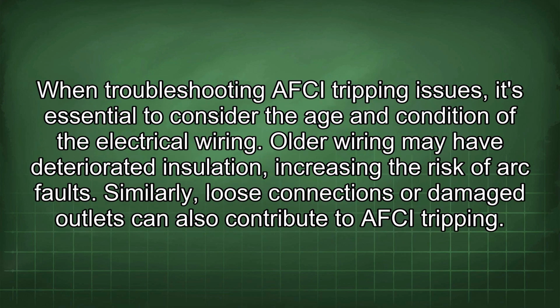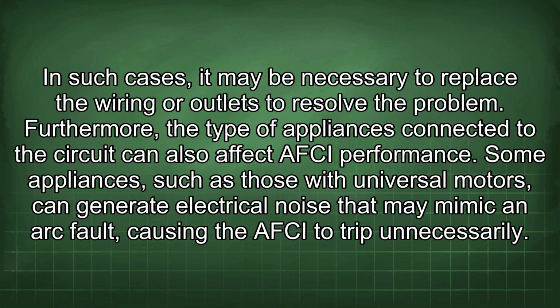When troubleshooting AFCI tripping issues, it's essential to consider the age and condition of the electrical wiring. Older wiring may have deteriorated insulation, increasing the risk of arc faults. Similarly, loose connections or damaged outlets can also contribute to AFCI tripping. In such cases, it may be necessary to replace the wiring or outlets to resolve the problem.